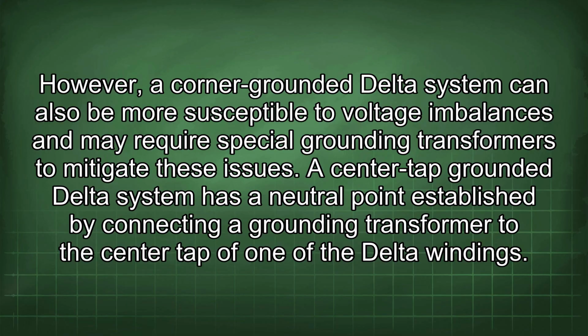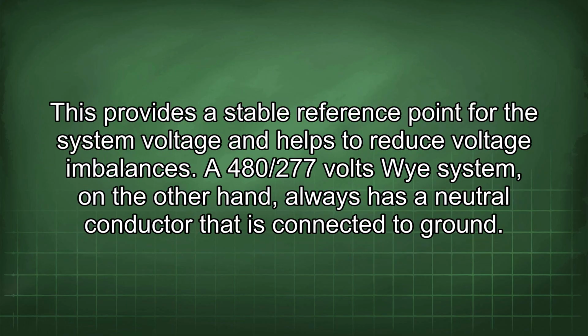to mitigate these issues. A center tap grounded delta system has a neutral point established by connecting a grounding transformer to the center tap of one of the delta windings. This provides a stable reference point for the system voltage and helps to reduce voltage imbalances.